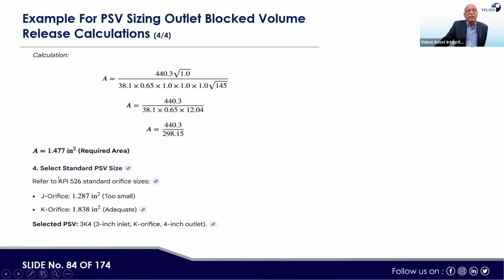Then we select the standard PSV size from the API 526 standard orifice sizes. J orifice is 1.287 and K orifice is 1.838. We cannot take the smaller one, it is too small. Then we have to take the next size, which is 1.838 square inch. And this is 3 by 4, 3-inch inlet, 4-inch outlet. This is the PSV sizing done. This way, PSV sizing and selection is done.